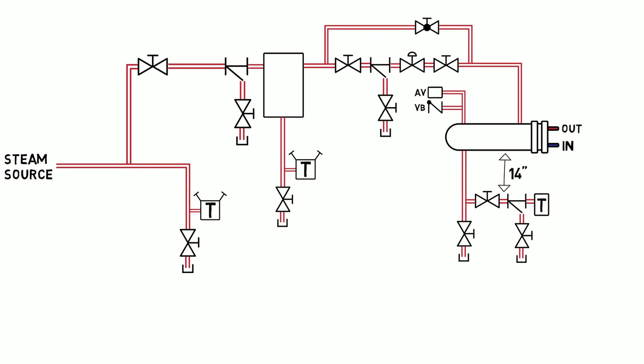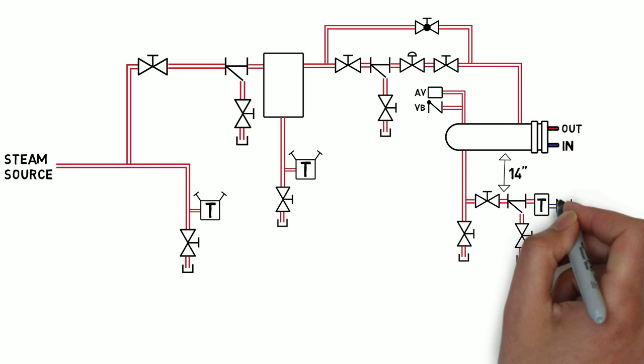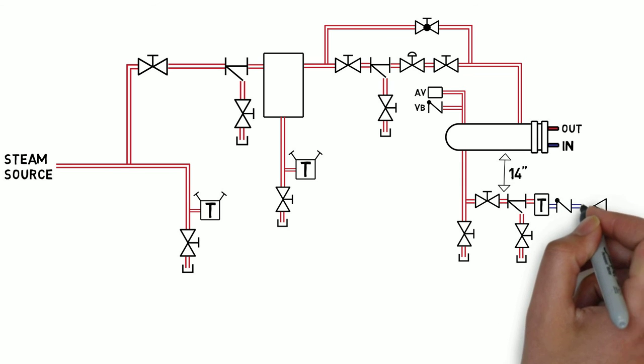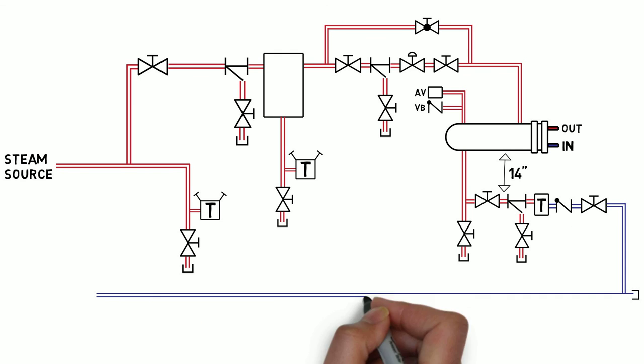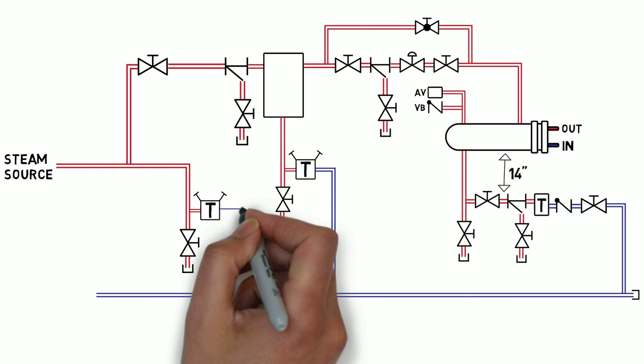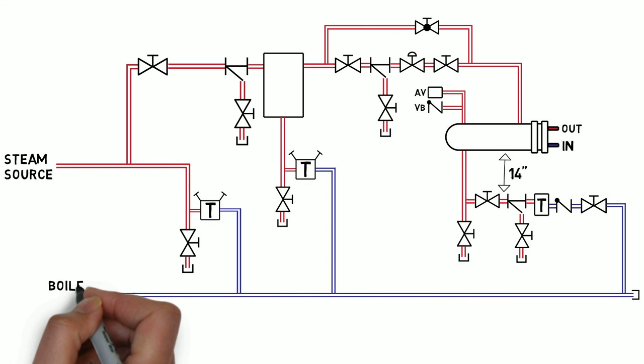After the steam trap, the condensate goes through a check valve and an outlet isolation valve. This condensate is piped horizontally and down to an atmospheric condensate return line, which picks up the discharge from the other steam traps and then returns to a condensate pump system or directly back to the boiler room.